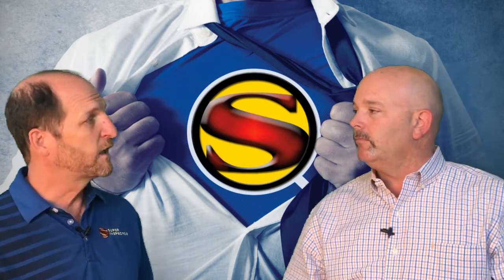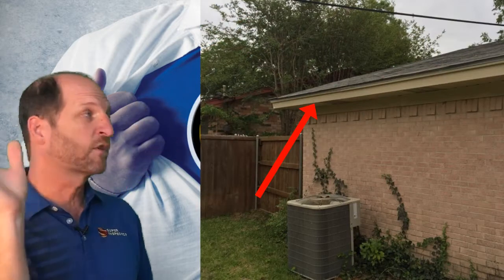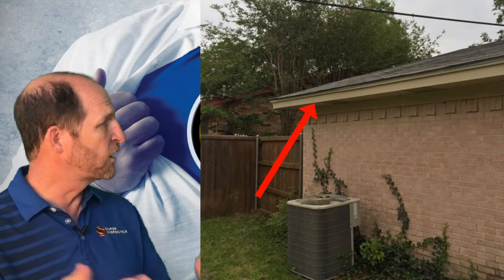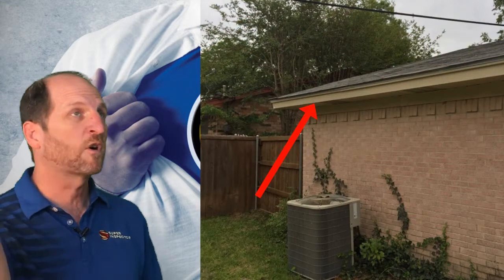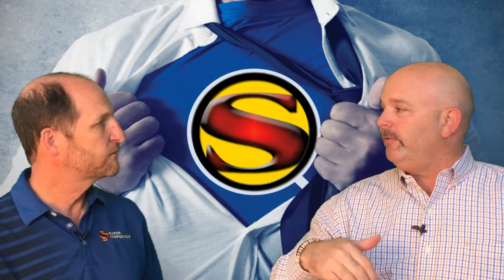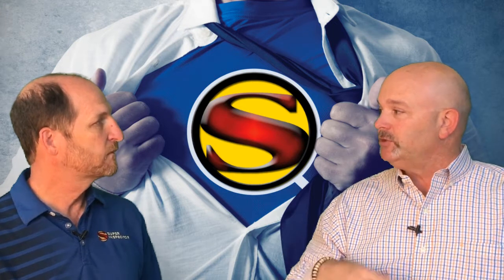And also, we look up on the roof. If there's not gutters on the house, there needs to be a diverter up there to divert the roof runoff away from the condenser. We don't want all the water coming off the roof down to the condensing unit. Because we've heard people talk before about the water running off of the roof, no gutter, no diverter, and it runs right down on top of the fan in there, and it causes rust.